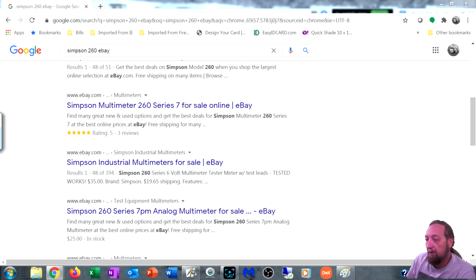So I had put the meter on voltage, but it was on 300 volts AC, so the scale was high. He was trying to read 3, and the meter was set to 300. The needle barely moved. So he's there showing the whole class. Well, before he connected this meter, I asked him, listen, I don't normally teach this to my class. We can do ohms tests on these microwaves and check these components out. Checking high voltage like that is not that safe. So I said, are you going to disconnect the high voltage lead?